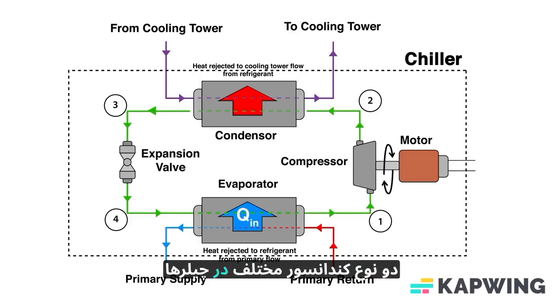There are two different types of condensers used in chillers, and the difference lies in whether a chiller is air-cooled or water-cooled. In a water-cooled chiller, the condenser is a tank like the evaporator, but this time water absorbs heat from the refrigerant instead of the other way around. The condenser water then travels to a cooling tower, often located on a rooftop, where the ambient air cools down the water before it returns to absorb more heat.